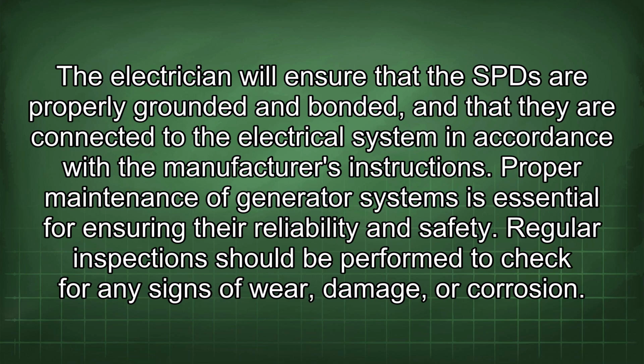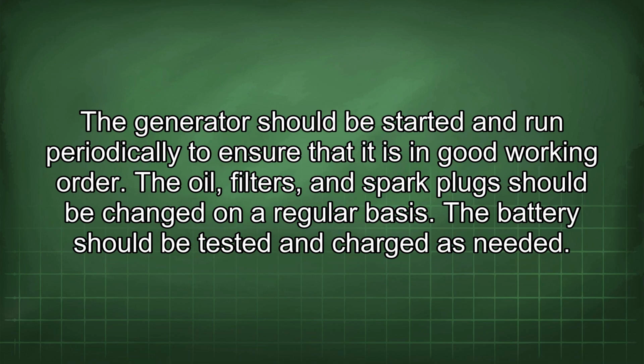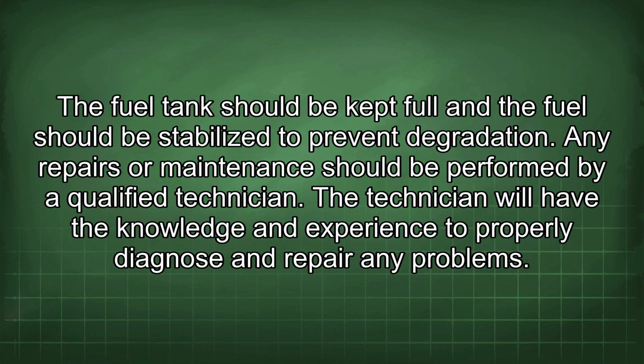Proper maintenance of generator systems is essential for ensuring their reliability and safety. Regular inspection should be performed to check for any signs of wear, damage, or corrosion. The generator should be started and run periodically to ensure that it is in good working order. The oil, filters, and spark plugs should be changed on a regular basis. The battery should be tested and charged as needed. The fuel tank should be kept full and the fuel should be stabilized to prevent degradation.